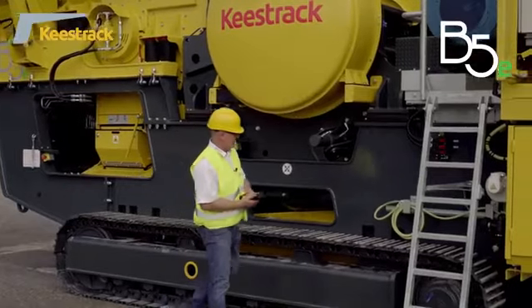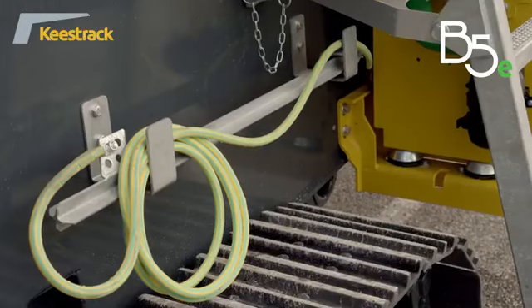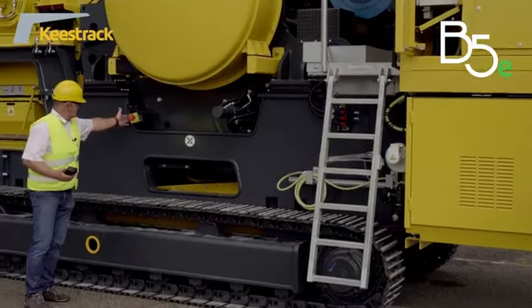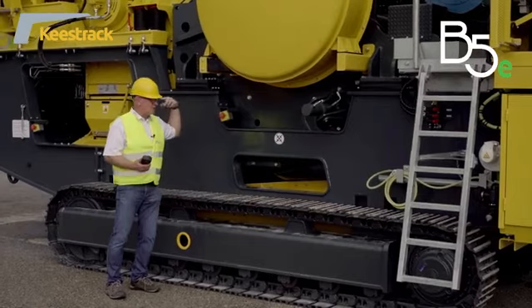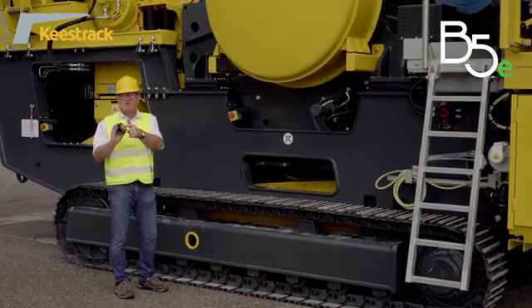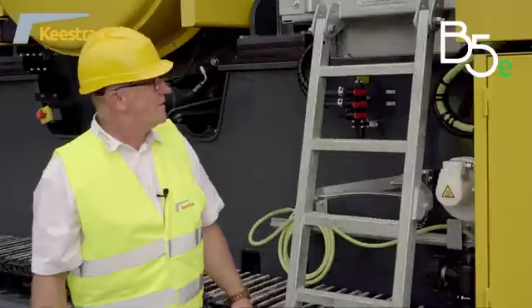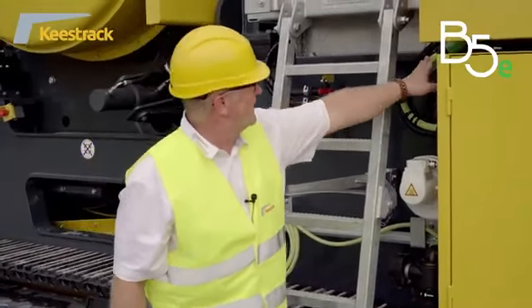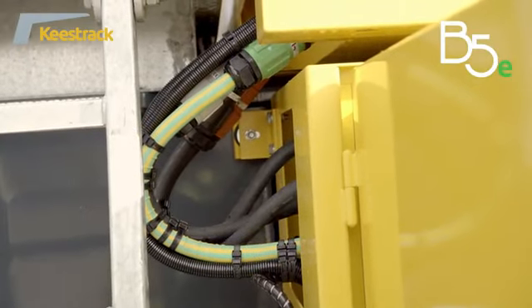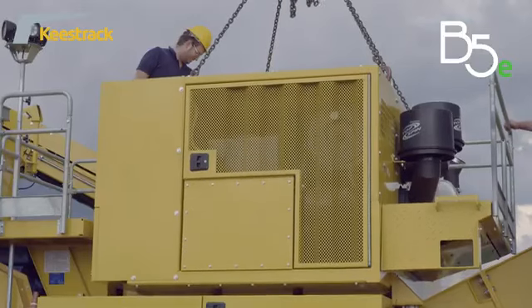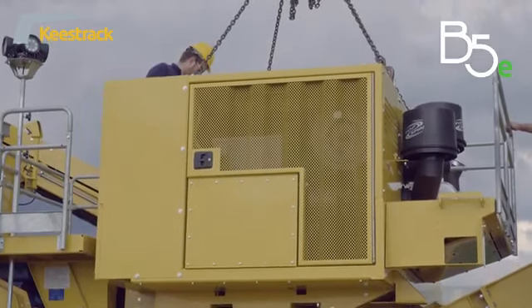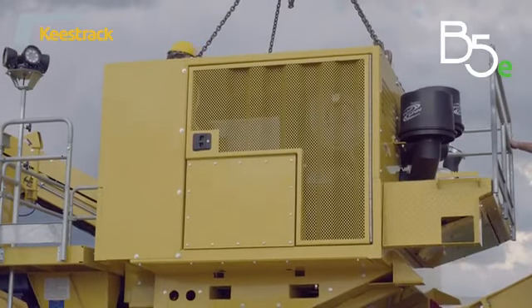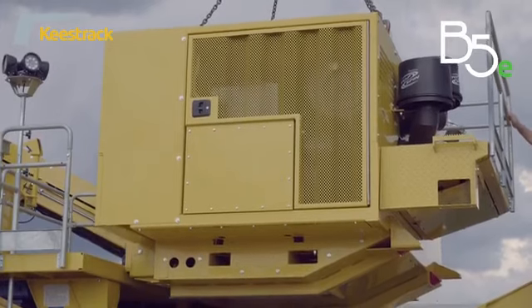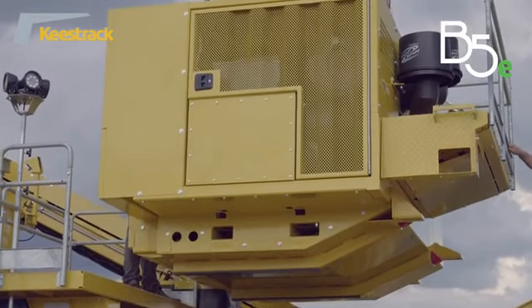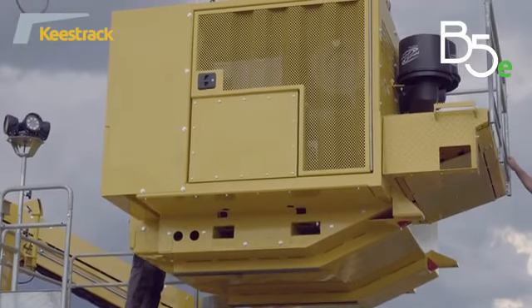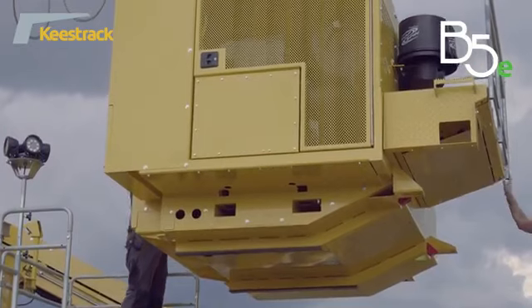So for safety, we have a grounding pin here for electric earthing. We have 7 emergency stop switches around the machine, and we have 1 blue machine stop button on the remote control. So for drop off of the engine unit, we have here power lock connectors which can be disassembled very fast. The engine unit can be removed and with cables we can supply the power to the machine. Even if the engine unit has some service or some fault, you can rent a standard diesel genset and connect the power up to here, or you supply power from your grid.